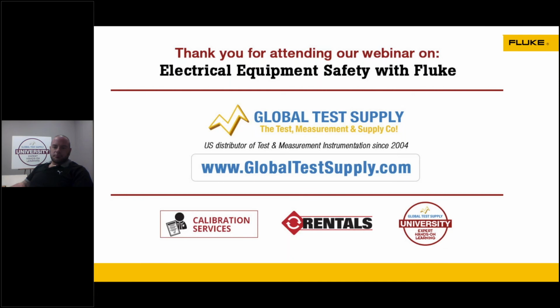Intrinsically safe means that when you're making electrical measurements, there could be little sparks happening internally to the meter. You don't see it, it's not causing any damage, but there could potentially be a little spark when you're making a voltage measurement. If you were in a hazardous zone, say oil and gas, with gas fumes around, and you were making that measurement without an intrinsically safe unit, there could potentially be a fault. There could be a blast because of that internal spark. So that's where an intrinsically safe meter is very valuable. There are additional safeties built in that don't allow that spark to come out of the meter in that hazardous zone. Now, that doesn't help you with potential arc faults or arc blasts.